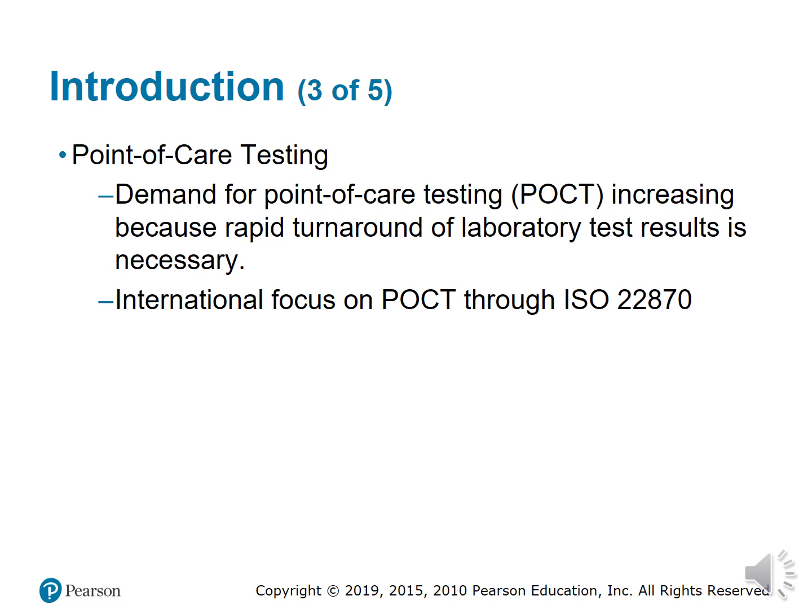They are called the International Organization for Standardization, or ISO 22870. Basically, they have special regulations for point of care testing that lies under them, which also lies under the Clinical Laboratory Improvement Amendment of 1988, or CLIA 1988.